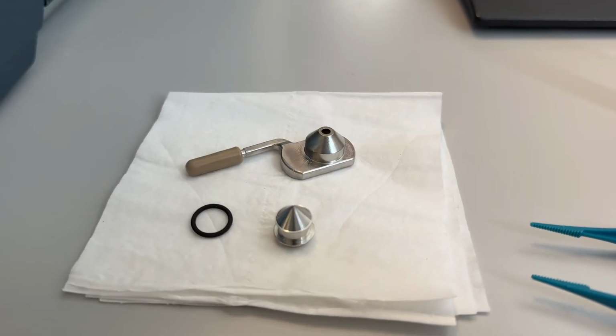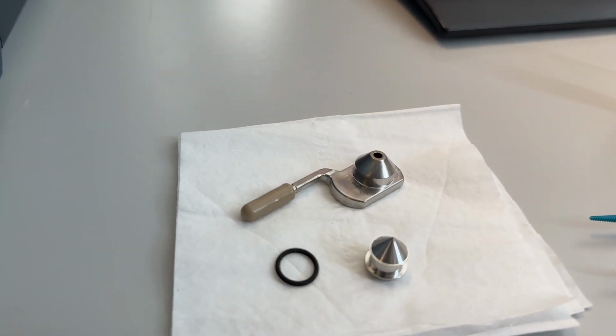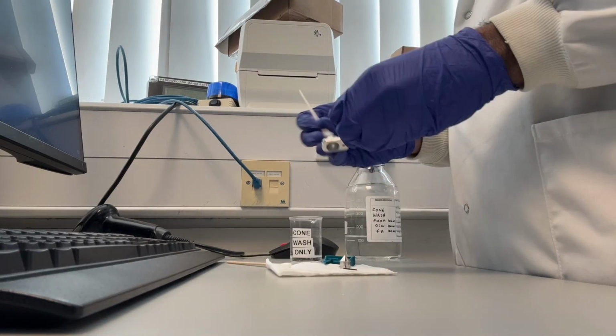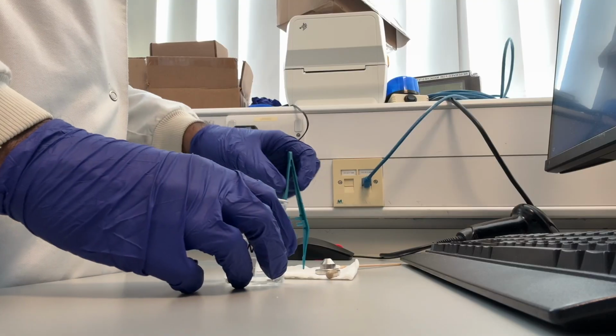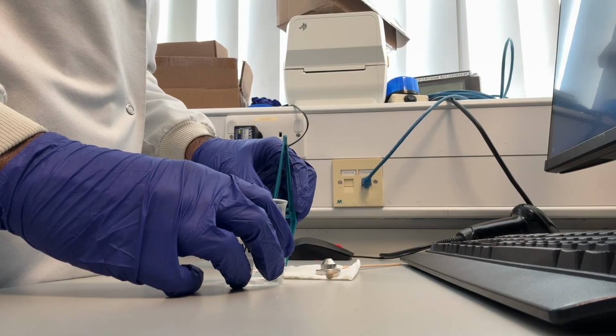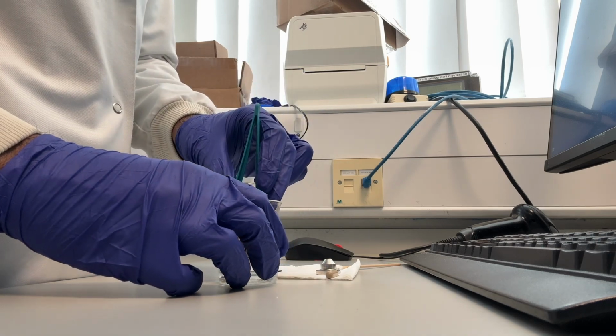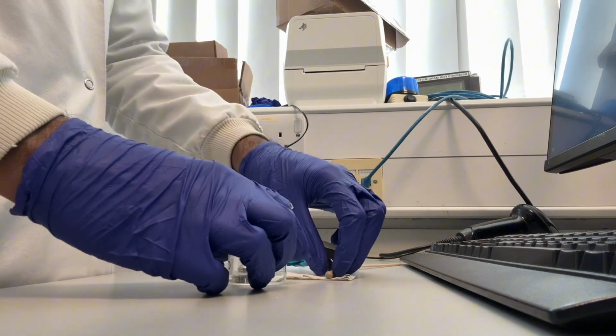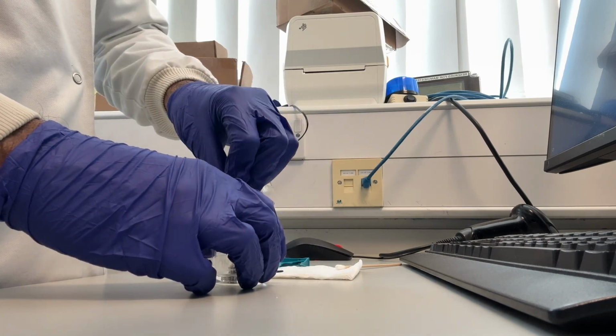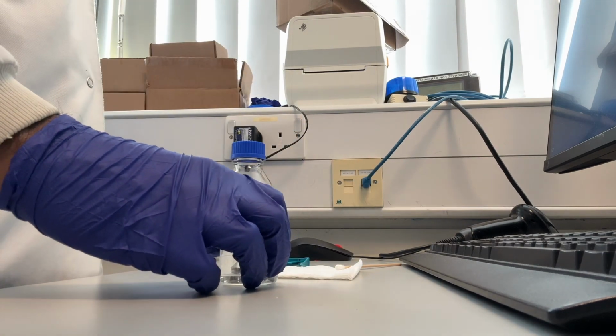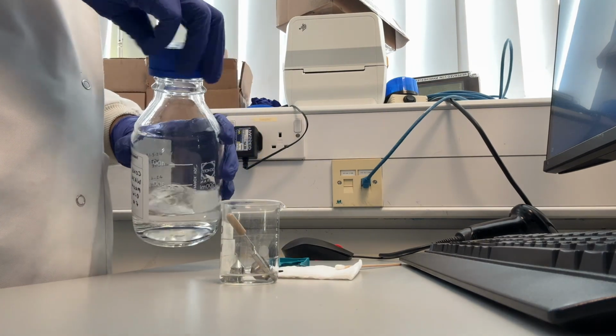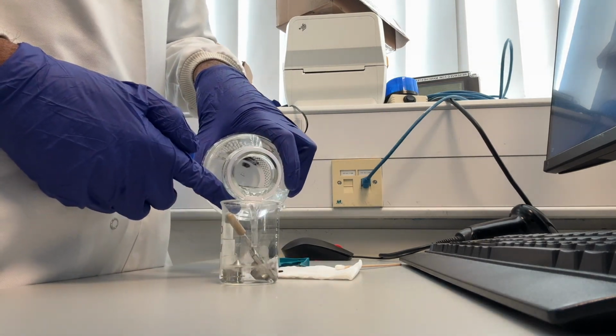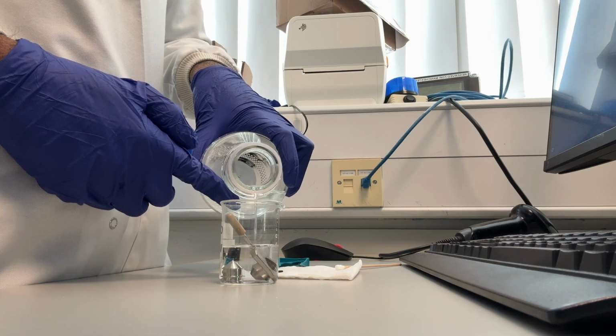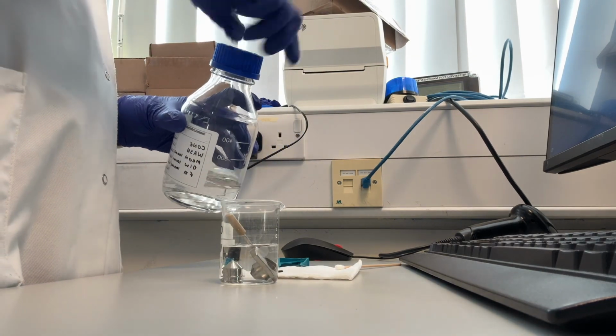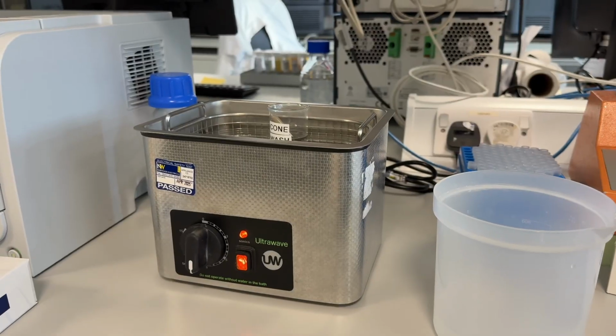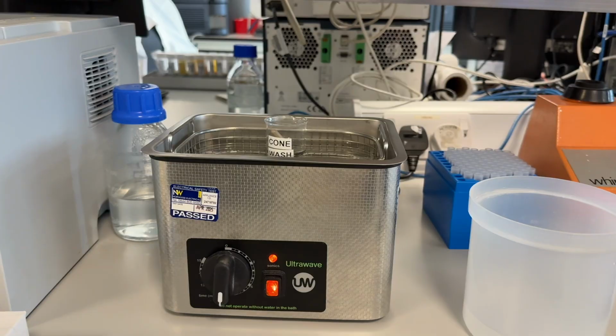Firstly, I make sure that the mass spec is not running, and then I stop the flow of gas. I then take out the module holding the cone and separate them into their components. I then give the housing a quick clean using the cone wash with swabs. After the cone has cooled, I will place the components in the cone wash beaker very carefully and add some cone wash. I'll then put this into the sonicator for 10 minutes.